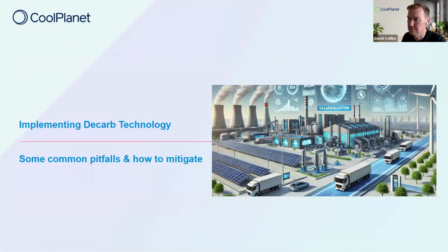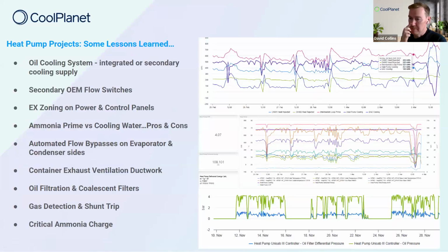Very quickly to finish up, some of the pitfalls when we talk about heat pumps—some of our own lessons learned. Oil cooling systems are very important because these are essentially refrigeration compressors, and the oil systems in them need to be cooled. Make sure you have a unit spec that either has integrated oil cooling, or you may need to bring a secondary source of cooling to the unit.